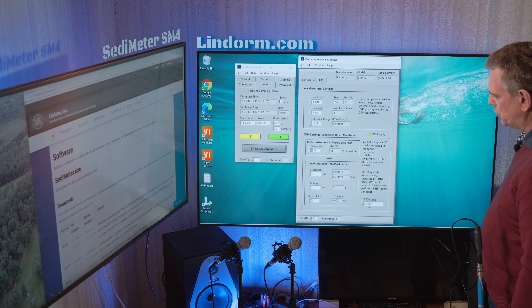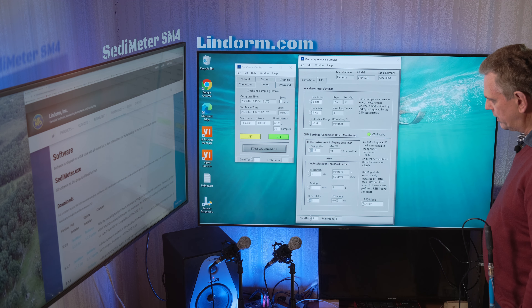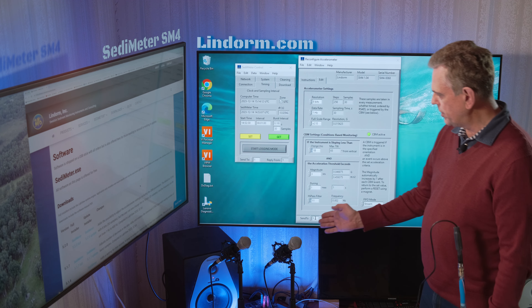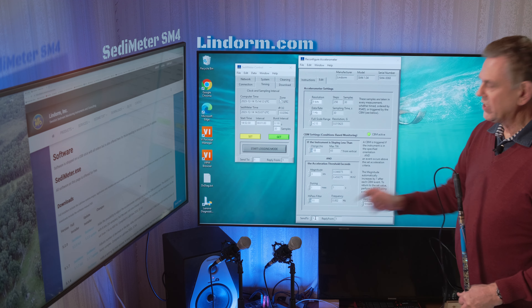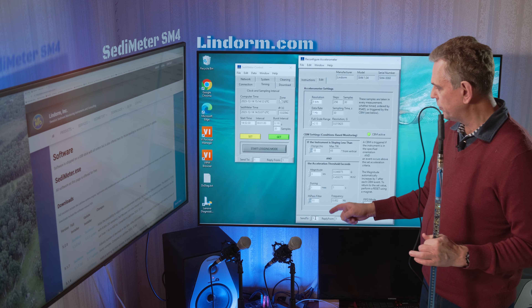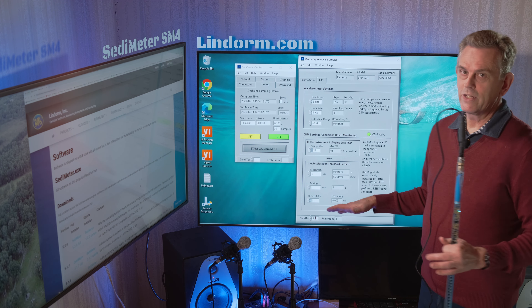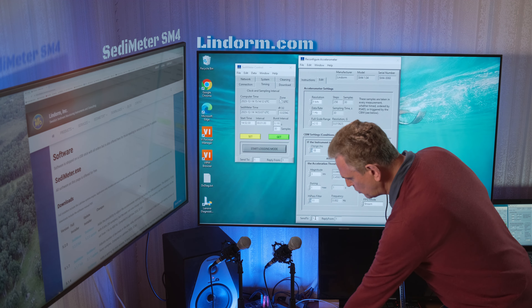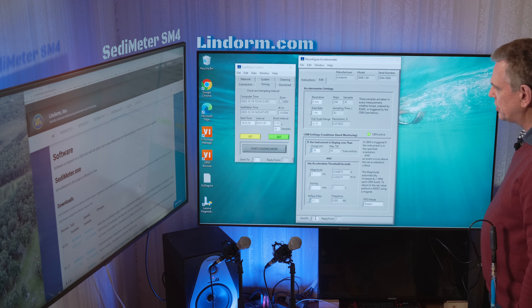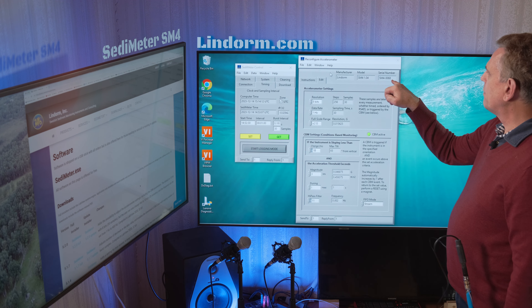For those who know about computers, the FIFO — first in, first out memory — the only mode supported now is stream mode, but it is available. Down here we have the same thing found in all windows: which instrument to send settings to. By default, each instrument has number one in the network. If you have a network with more than one instrument, you need to give them individual numbers. Note that changing the instrument number here doesn't make much sense, because to take effect you would need to go to the instrument with a magnet and reset it anyway.